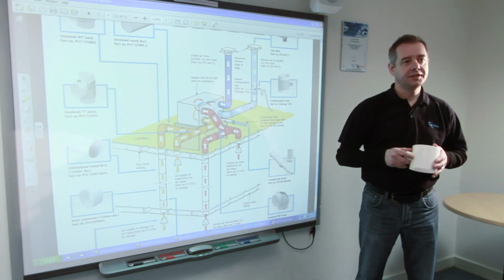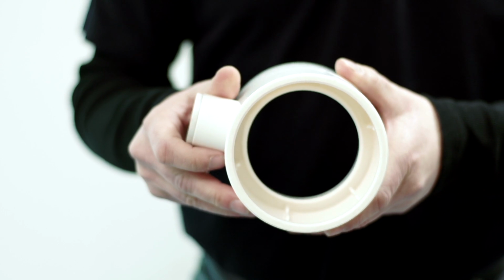The current regulations also state that any ducting rising vertically carrying extract air to outside requires the use of a condensate trap. This is to prevent any moisture from forming inside the ductwork from dropping back down and getting back into the fan, causing damage.